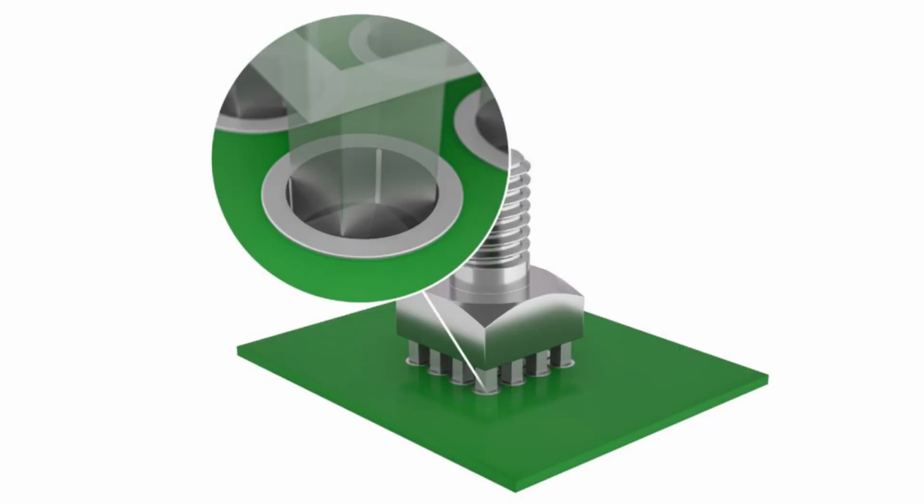By pressing the pins directly into the PCB, there's a strong friction between the pin and the plated through hole, creating a seamless cold welding connection between the pin and the copper-plated via within the PCB. This delivers a secure, gas-tight, and mechanically strong connection with a contact resistance of less than 200 microohms. No other technology matches the ability to handle currents up to 250 amps with such minimal self-heating.